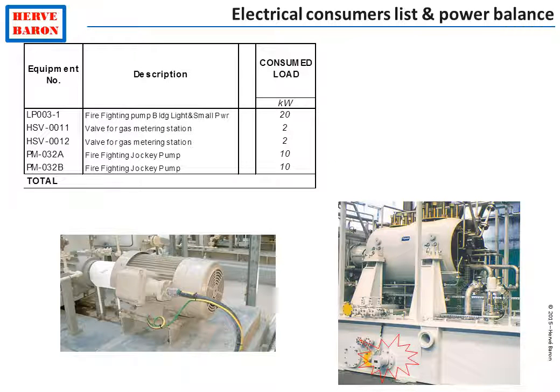The starting point of the electrical engineer is to draw the electrical consumers list. It consists of making an exhaustive inventory of all plant electric power consumers. These include obvious process consumers such as pumps, as well as some hidden consumers such as a lube oil heater inside a compressor package.